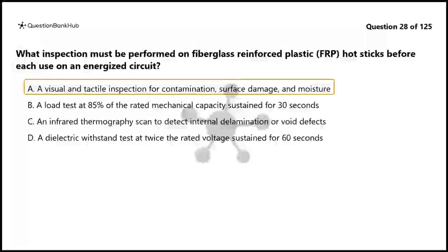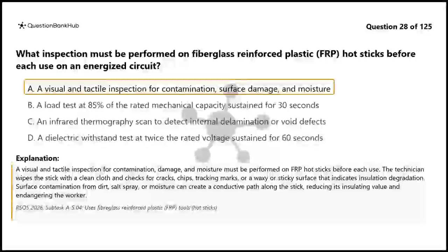The correct answer is A. A visual and tactile inspection for contamination, damage, and moisture must be performed on FRP hot sticks before each use. The technician wipes the stick with a clean cloth and checks for cracks, chips, tracking marks, or a waxy or sticky surface that indicates insulation degradation. Surface contamination from dirt, salt spray, or moisture can create a conductive path along the stick, reducing its insulating value and endangering the worker.